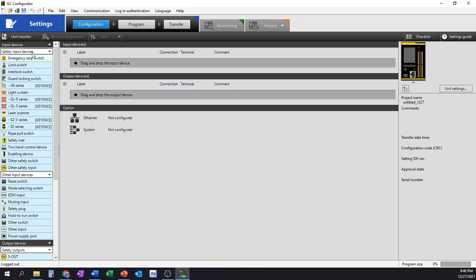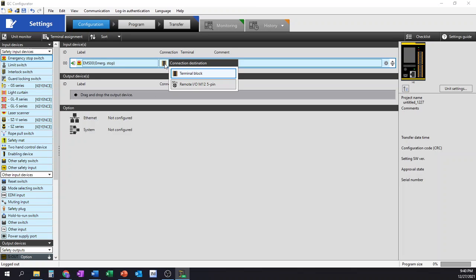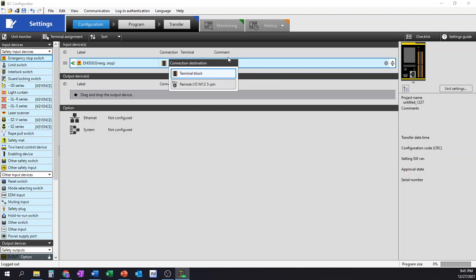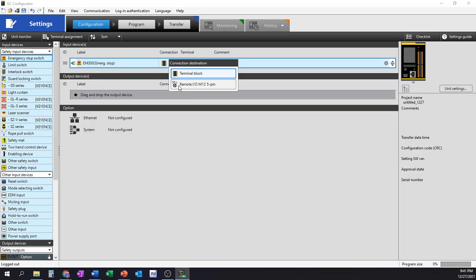The very first one they give us is an emergency stop function. We can drag that over to get a feel of what it is. Most of us are familiar with the emergency stop push button if you had anything to do with safety. With this control function you have the ability to plug it in as a terminal block, so direct discrete wiring into the functional terminal blocks on the controller itself, or you also have the option to use it as a 5-pin remote I.O. through the Keyence remote I.O. terminal blocks. We're going to leave it connected directly to the terminal block. I'll explain the 5-pin terminal block later when we get into talking about the gate switches.